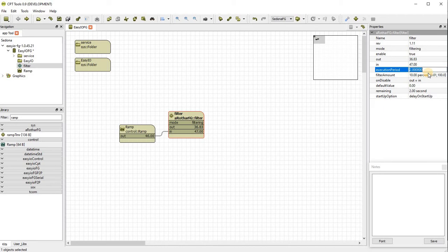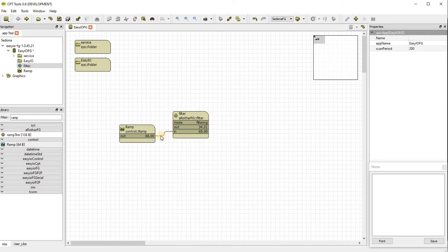So to slow it down, you can make that every 5 seconds. Or alternatively, you could change the percentage as well. Either way, it's going to change. And you can see this averaging value follows the input. So it's good for air pressures that are bouncing around a fair bit, water pressures that are bouncing around a fair bit. But there are things to be careful of if you're going to use it in that kind of application. Not just our filter, but everybody's filter is the same.